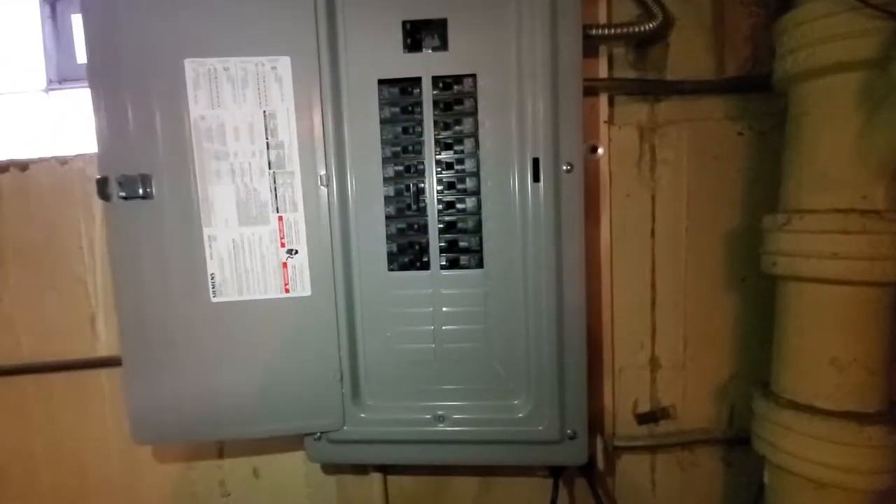installed by us. This is a Siemens box, and the AC breaker is a 30 — we'll need to drop that down to, I believe, a 20 or a 25. I'll double check and put that in an email.